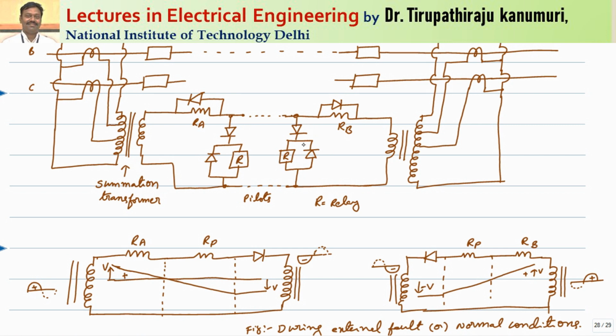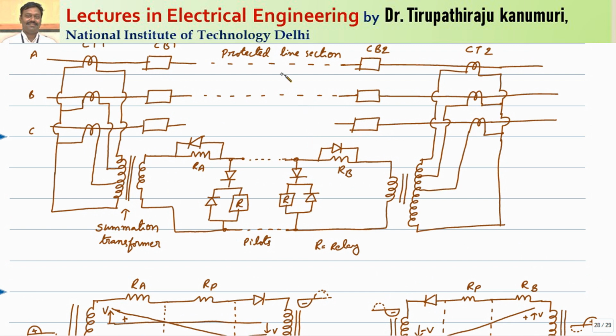So let us take the case of internal fault. That means some fault happened internal to this one. So whenever an internal fault happens, automatically the currents produced by the two CTs are different. So automatically the voltage at the sending end will be greater than the voltage at the receiving end. This can be one case.